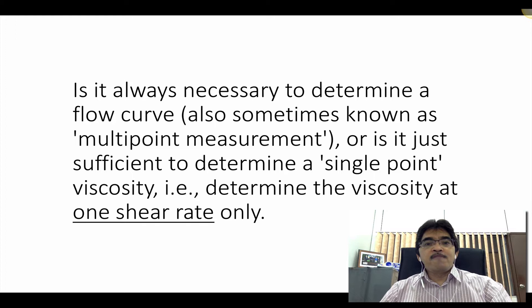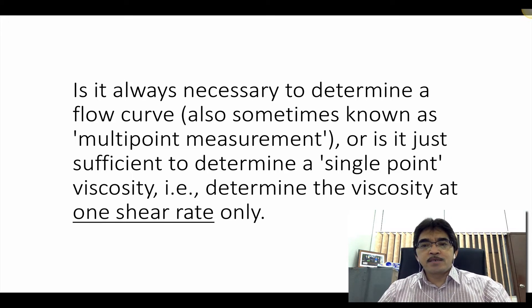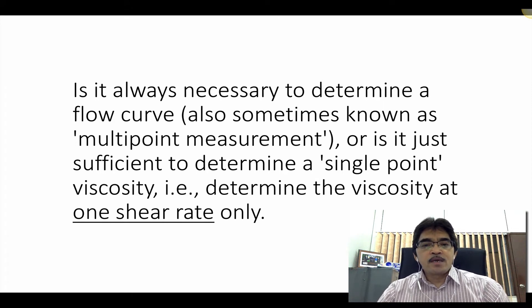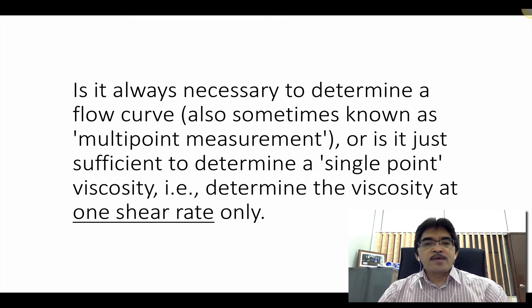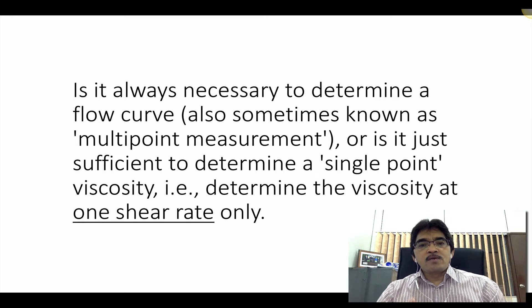Is it always necessary to determine a flow curve, also sometimes known as multipoint measurement, or is it just sufficient to determine a single point viscosity, which means that we determine the viscosity at one shear rate only, one constant shear rate? For these questions, we have to think about what is the type of sample or the material or the liquid that we are measuring, whether it's a Newtonian or a non-Newtonian.